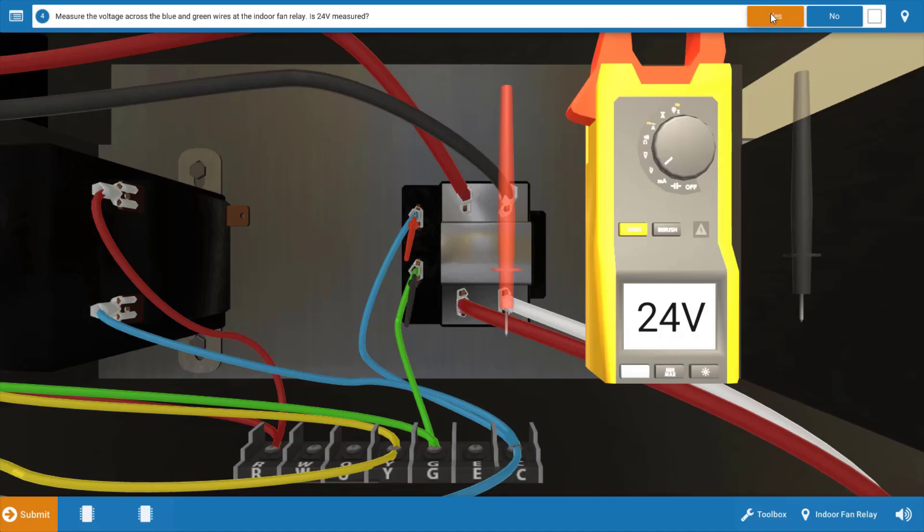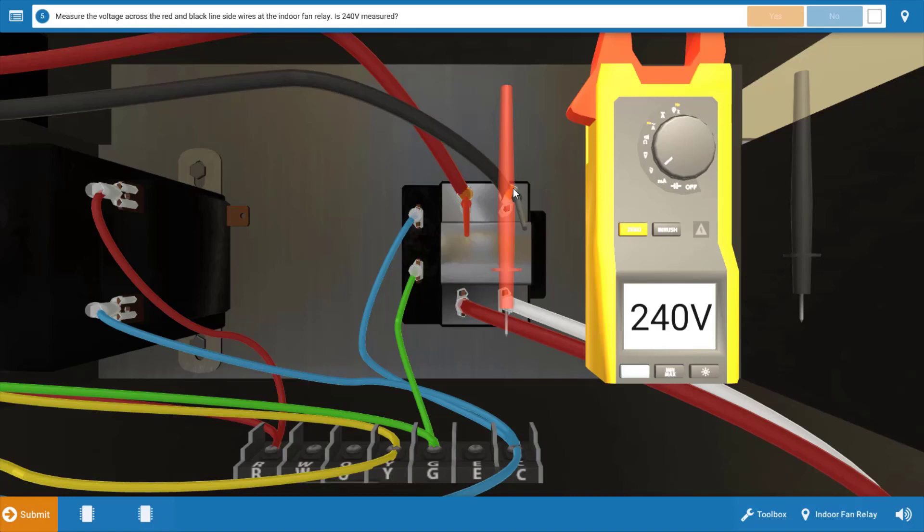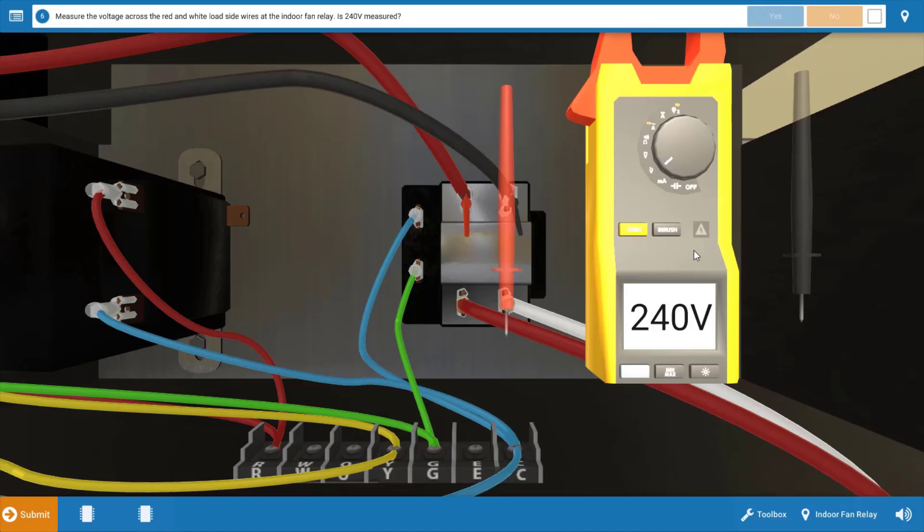So after clicking yes on the procedure guide that we've measured 24 volts, we're going to measure for line voltage coming into the indoor fan relay. And this is just going to verify we don't have any breaks in the connection or possibly wire nuts. And we do have 240 volts coming into the line side of the relay. So we're going to click yes.